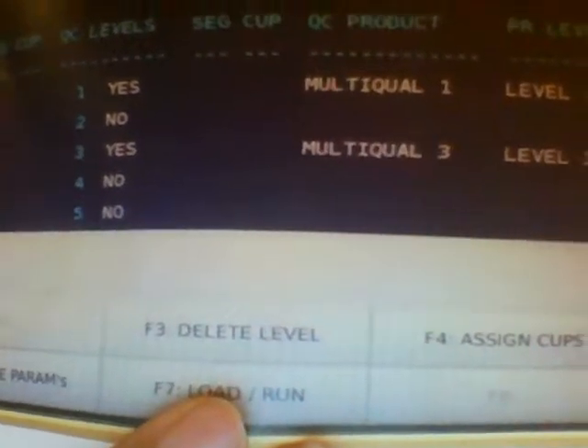So once you have selected the lot you wanted, and you have a starting position, you're going to choose F4. Okay, F4, assign cups. And once you push F4, you're going to get a printout that shows you all the cups and where the calibrators go. It's very important to look at those cups in the calibration, because sometimes calibration 1, calibration 2, calibration 3 are not in order. And you don't want to misorder your calibration because it's messed up and then you have to do it again. It kind of sucks.